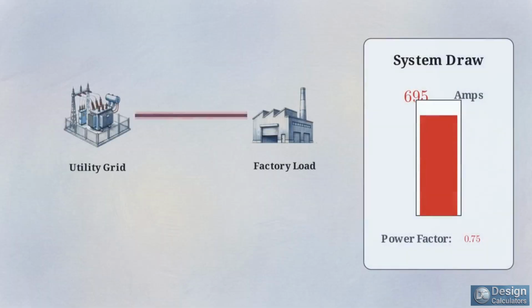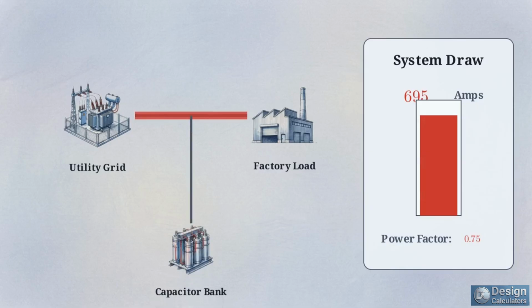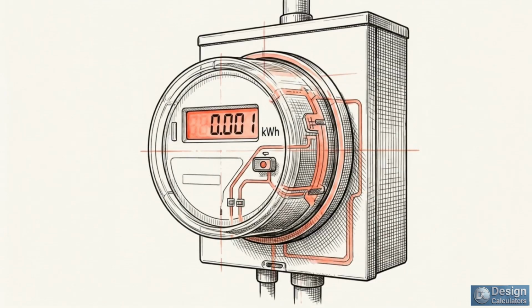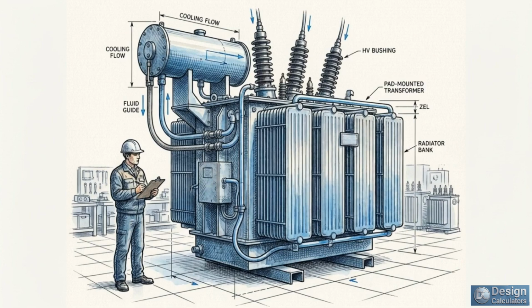Operating at a poor power factor of 0.75 pulls a massive 695 amps, causing cables to overheat. Installing a capacitor bank supplies reactive power locally, cutting extra utility demand. This improves the ratio to 0.95 and drops the draw to 548 amps. By simply correcting the ratio, nearly 150 amps of current vanish from the grid. This eliminates the excess heat and utility penalties, all without altering the factory's output.